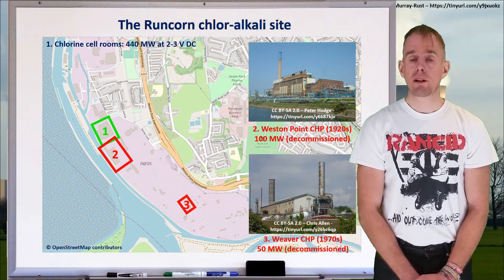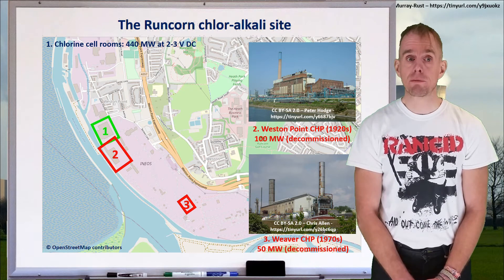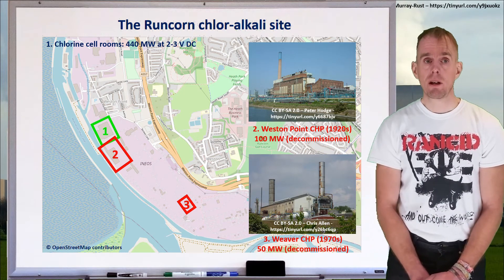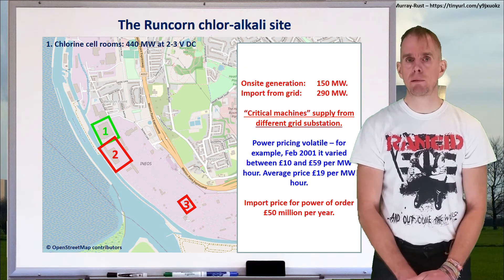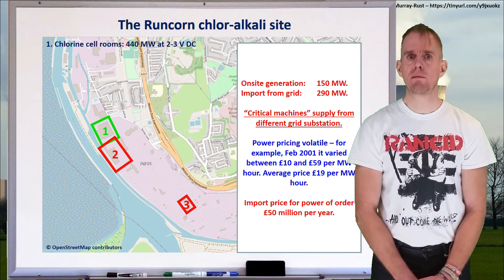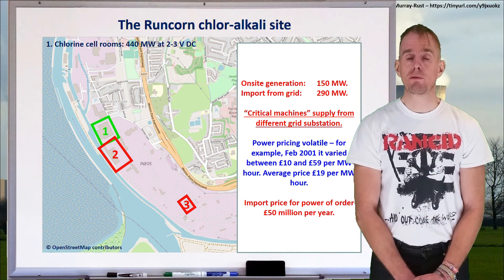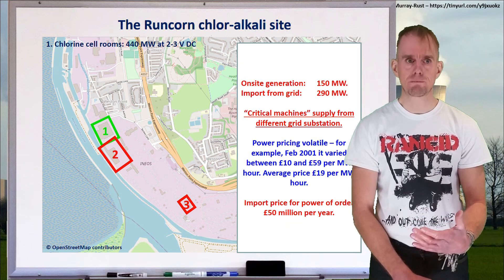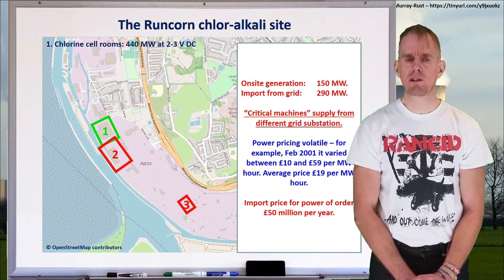In the 1970s, another combined heat and power plant was built on site — the Weaver CHP — supplying 50 megawatts of electrical power and steam. So onsite generation up until the early 1990s was about 150 megawatts electrical, meaning 290 megawatts had to be imported from the grid. It should be noted that the supply to critical machines — such as chlorine scrubbers — was sourced from a different part of the grid, so that if the main power supply failed, these critical pieces of equipment would still continue to work.